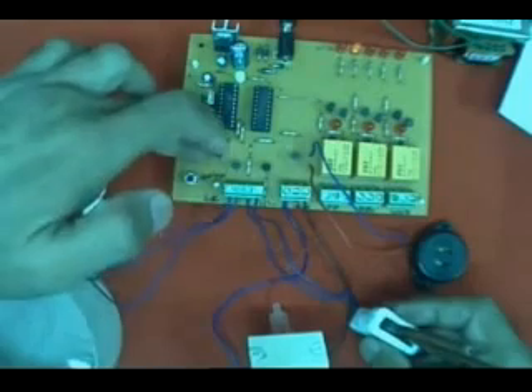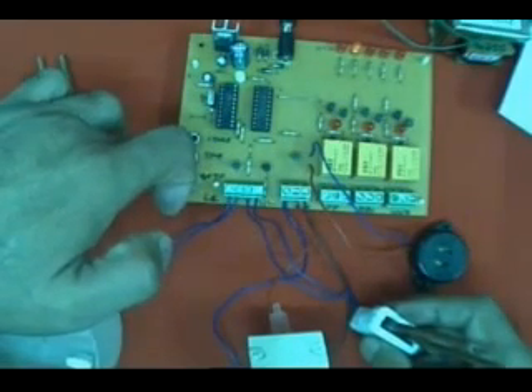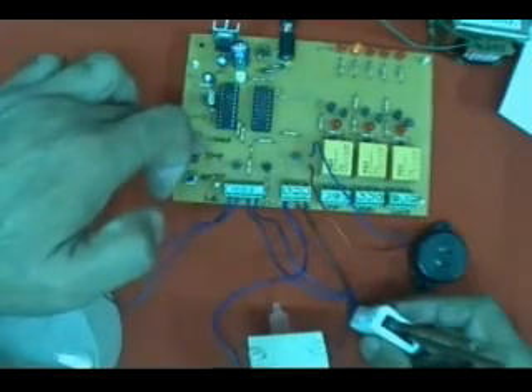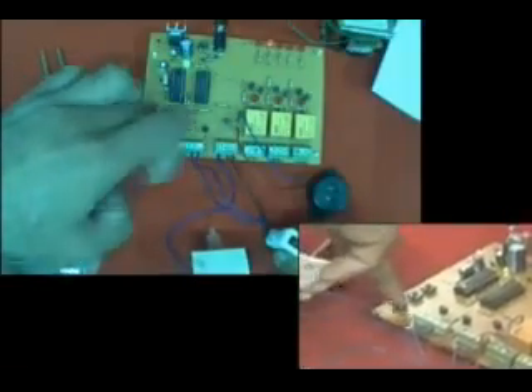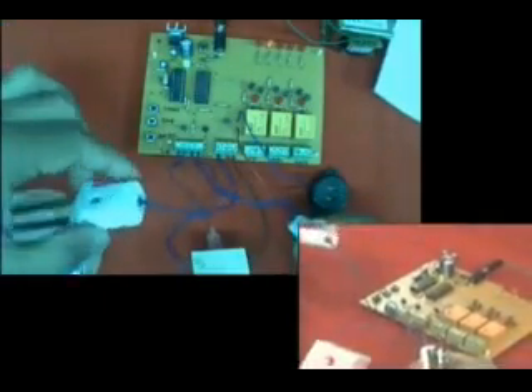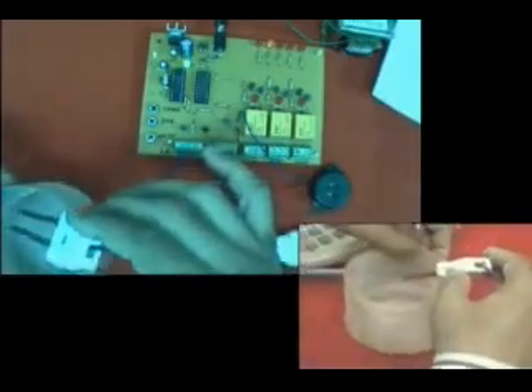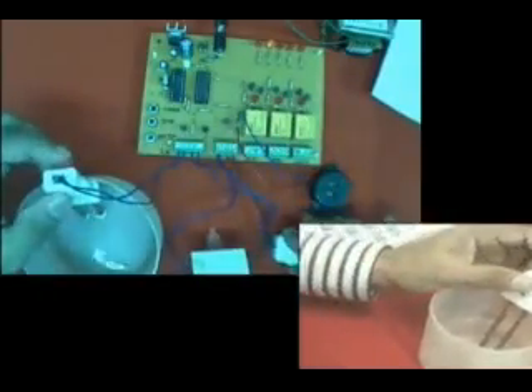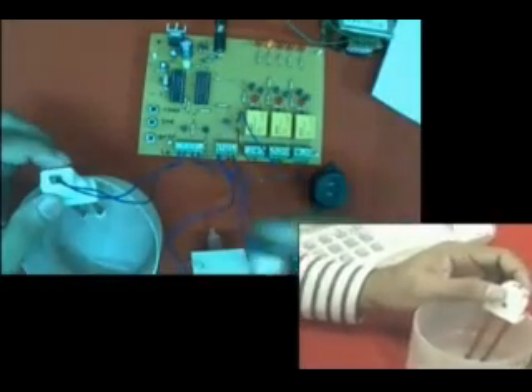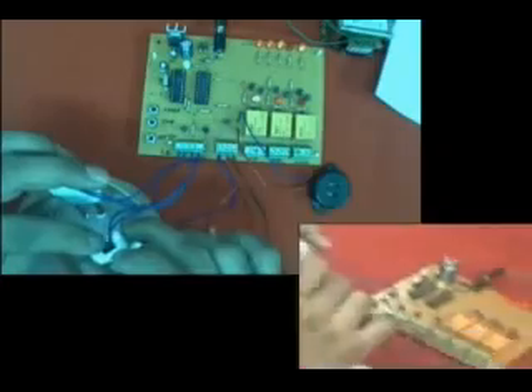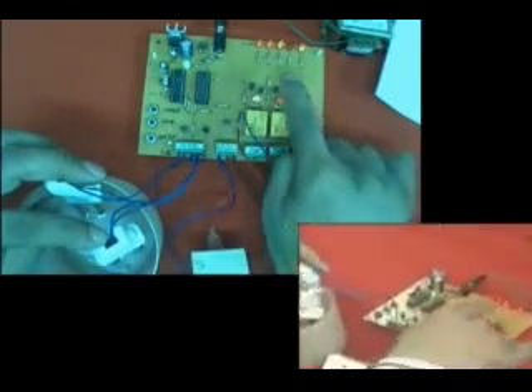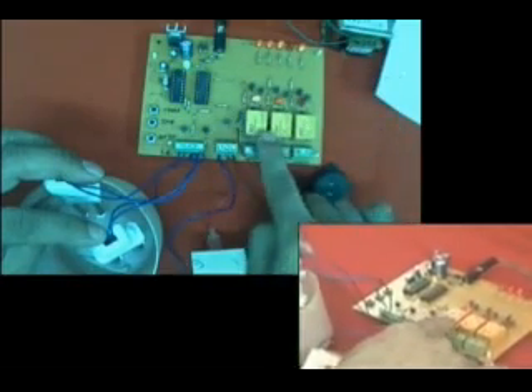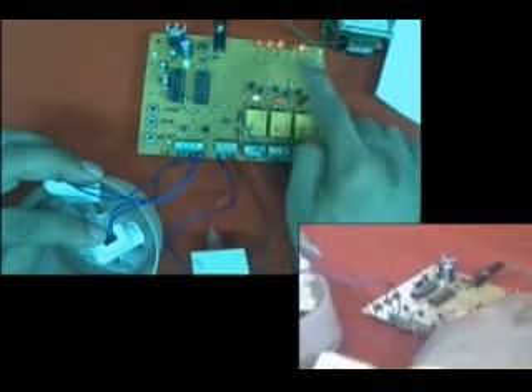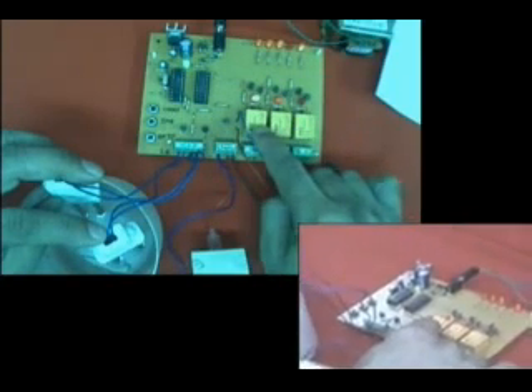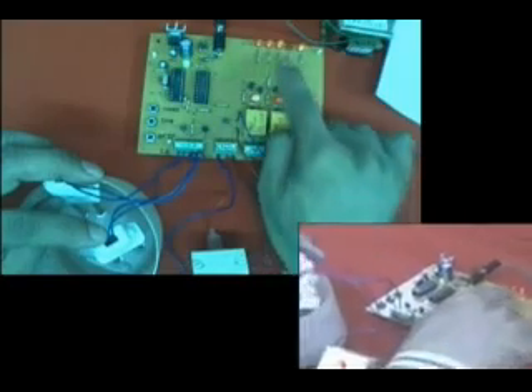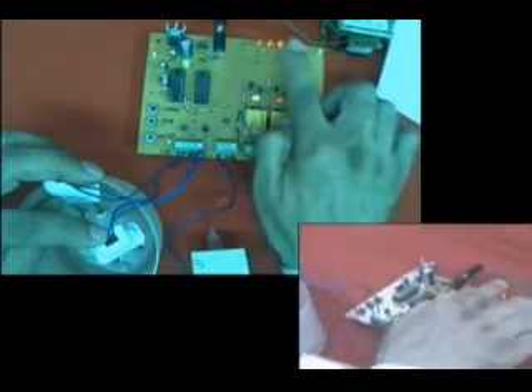Anytime I can stop it. When you press auto, the plant is in auto mode. Now you cannot start in manual mode. Now this is the lower level, so first dip this lower level into the water and slowly the bilges will rise, and then the water will come to the upper level. When the water comes to the upper level, the indication says the water is at upper level and these two are on. This indicates that the overboard valve is open. This indicates the pump is on, and this indication is high level and plant is in auto mode.